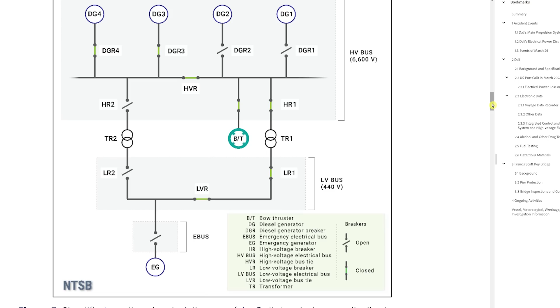So it looks like this is the one — they're talking about diesel generator number 2. They were making adjustments on it when he closed the damper, and it caused the engine to stall out, so they lost power on this. It was the only generator at that moment putting voltage onto the high voltage bus, so of course that takes out power to the whole ship at that time.